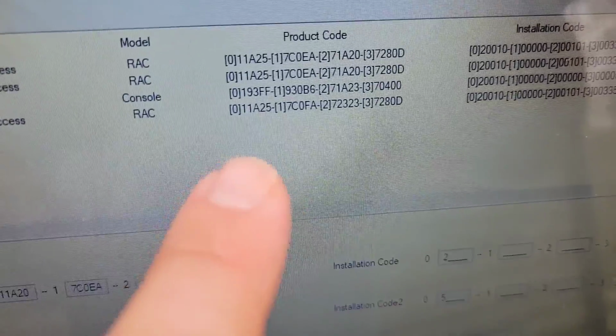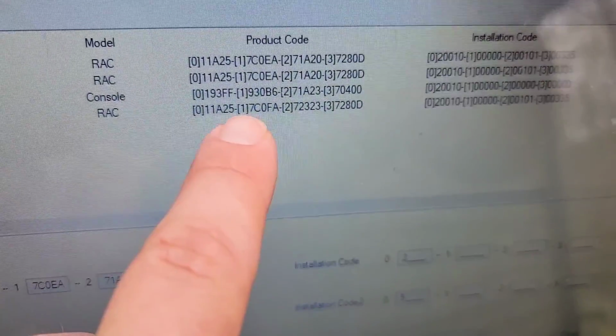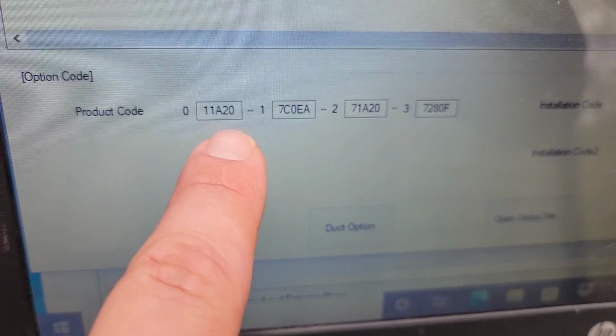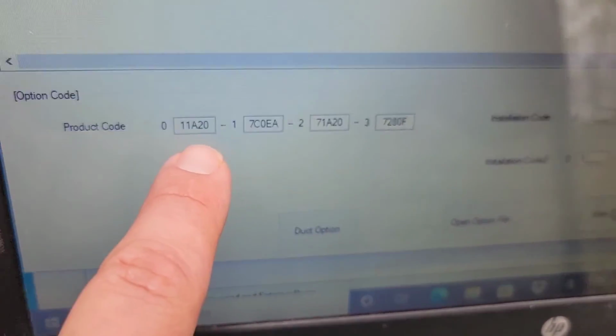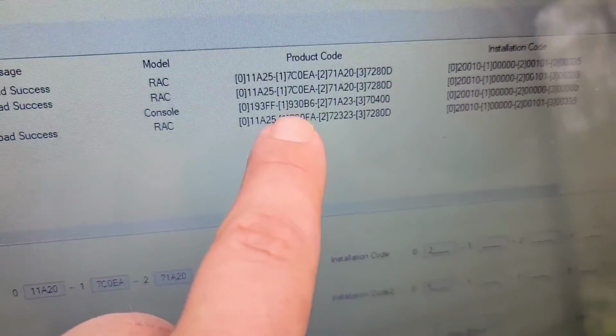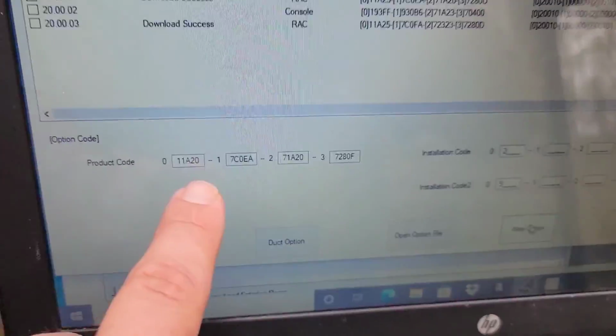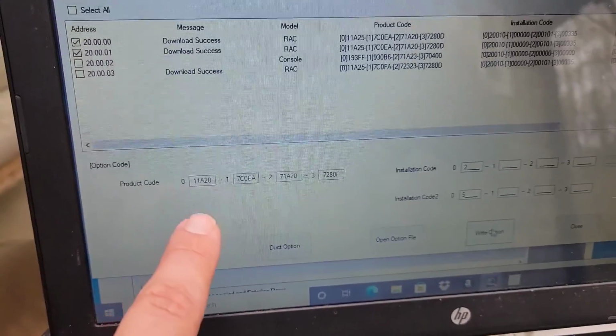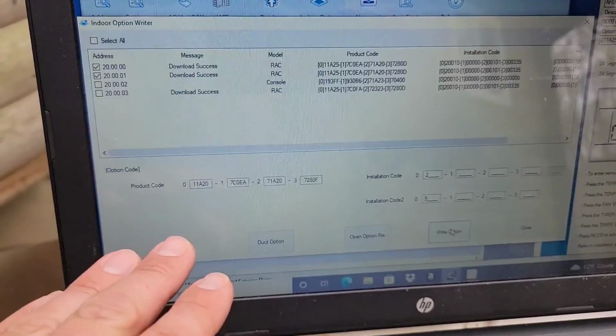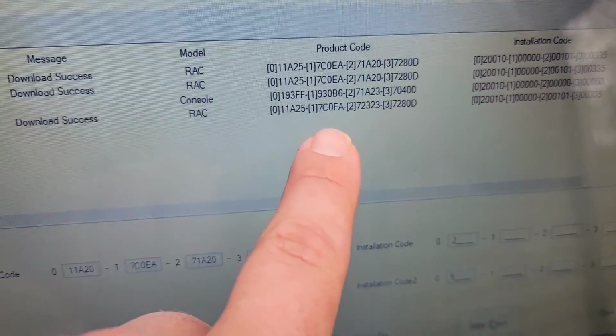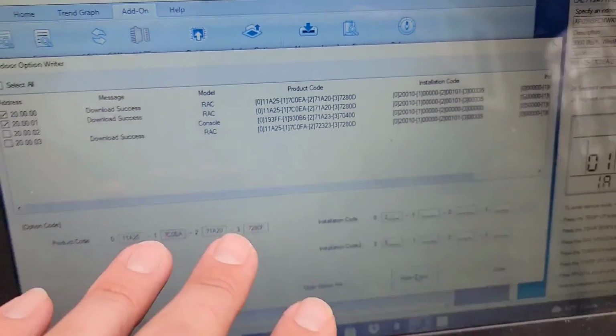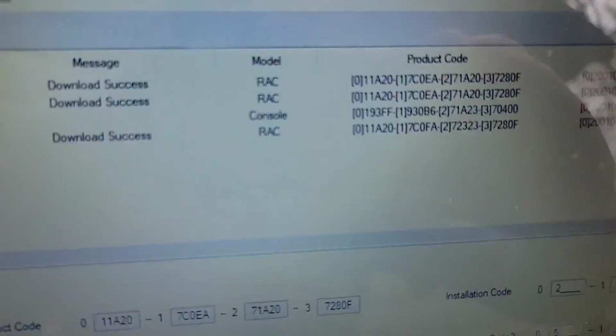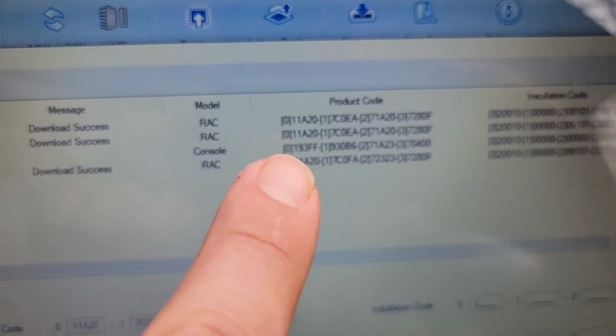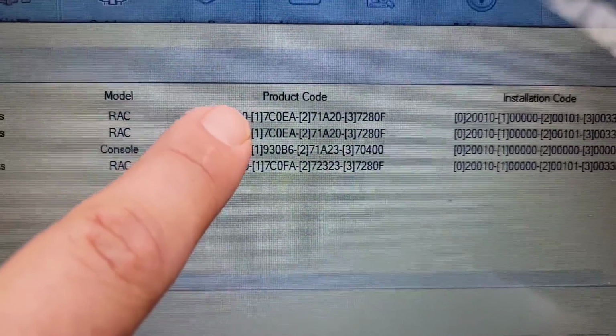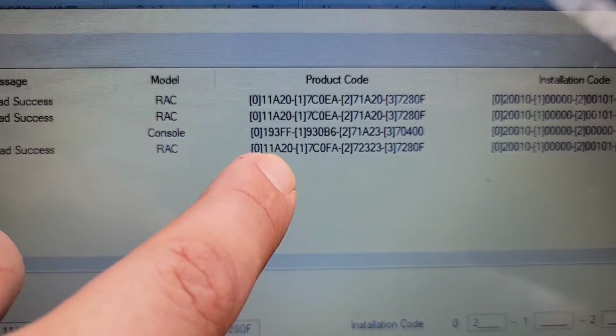And also, you can see where this says 5 here, right? When I do my option code, I'm putting a 0 there because that is heating compensation. You do not want your indoor units to read a temperature that is higher than what it actually is in the room. So I'm making that 0, and I want to make sure that changes, because if it doesn't, then I'm going to re-option code. Okay, so you can see how the product code has changed now. It no longer says 5 after the 2, it says 0.